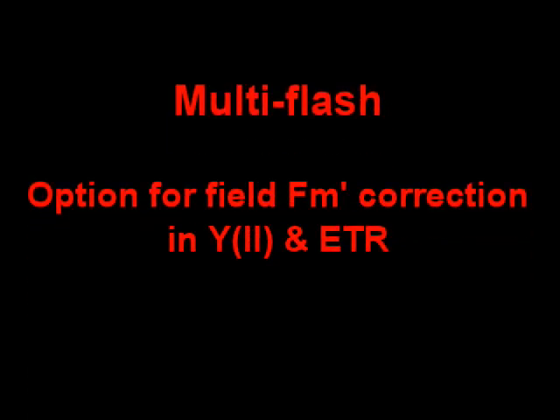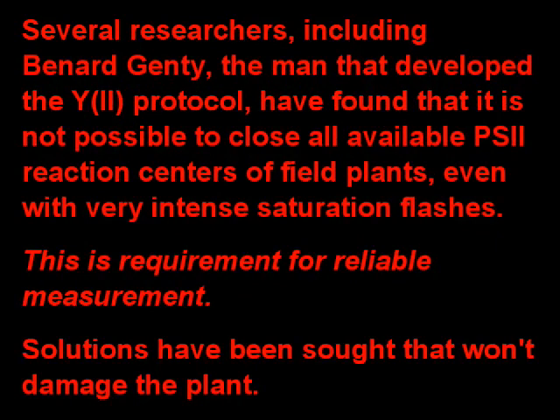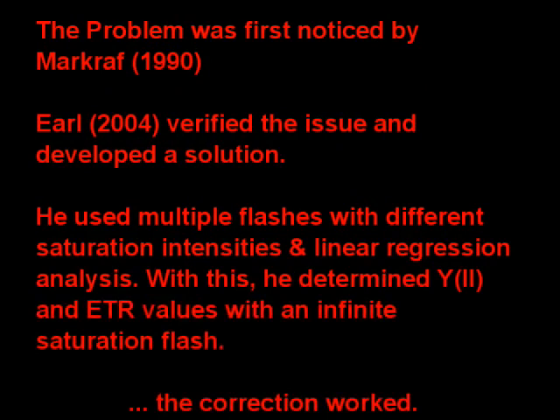Multi-flash is an option for field correction of FM prime in yield and electron transport rate. Several researchers, including Bernard Genty, the man who developed the yield protocol, found that it is not possible to close all PS2 reaction centers of field plants even with very intense saturation flashes. The problem was first noticed by Markraf in 1990. Earl, in 2004, verified the issue and developed a solution using multiple flashes with different saturation intensities and linear regression analysis, allowing yield and ETR values to be determined with an infinite saturation flash.